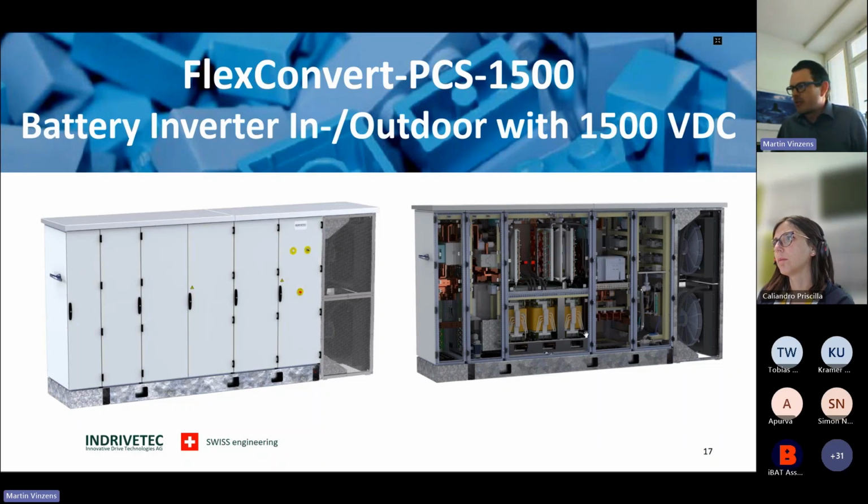Here you see a picture of how it looks. So here we have the power stacks as shown before, the filtering inductors, AC, DC connection, and so on. Here on the right side, we have the heat exchangers to cool down the liquid water glycol mixture, which is cooling the inductors, the power electronics, and the air inside the cabinets.